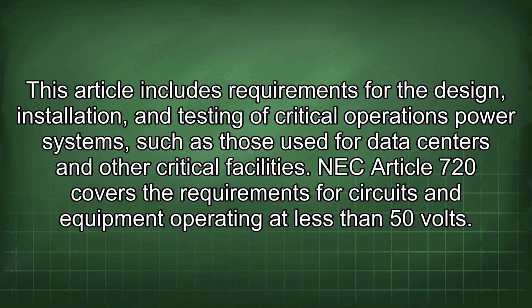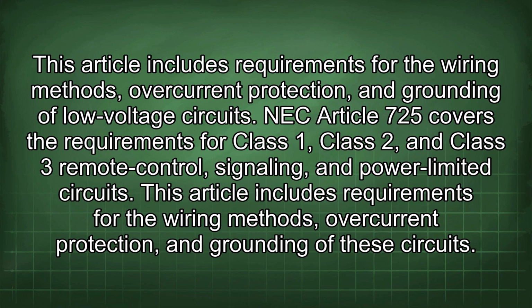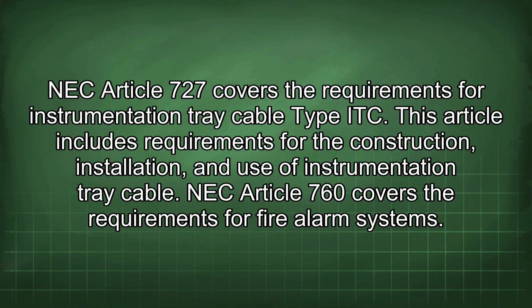NEC Article 720 covers the requirements for circuits and equipment operating at less than 50 volts. This article includes requirements for the wiring methods, overcurrent protection, and grounding of low-voltage circuits. NEC Article 725 covers the requirements for Class 1, Class 2, and Class 3 remote control, signaling, and power-limited circuits. This article includes requirements for the wiring methods, overcurrent protection, and grounding of these circuits. NEC Article 727 covers the requirements for instrumentation tray cable type ITC. This article includes requirements for the construction, installation, and use of instrumentation tray cable.